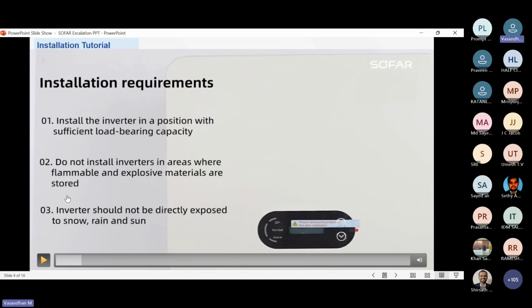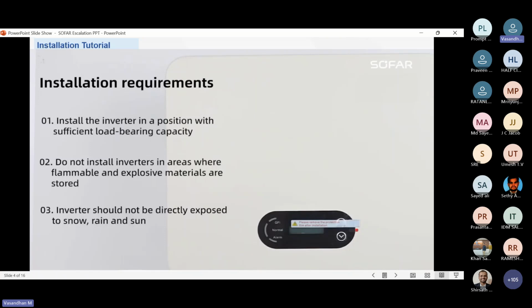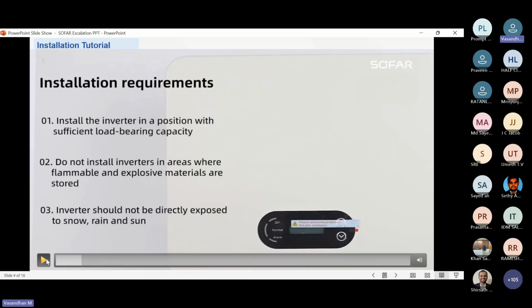Installation requirements. Install the inverter in a position with a sufficient load bearing capacity, that I already told. Top, bottom and backside bracket to inverter, that measurement we need to check with the user manual. And do not install the inverter in areas where flame or explosive material are stored. Everyone commonly knows this. And the inverter should not be directly exposed to snow, rain and sun. This is IP66 only, so no need to worry about that, but they mentioned it for safety purposes.